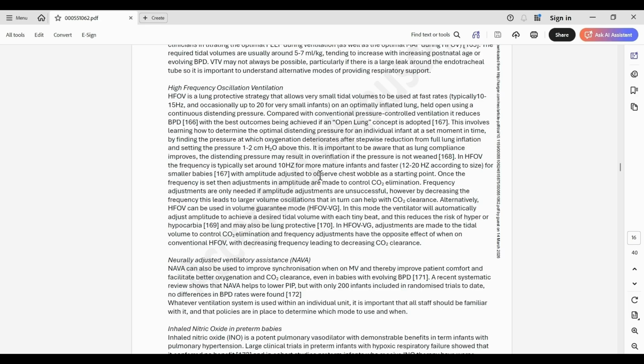But you can't just go ahead and throw kids on the ventilator or the oscillator without really knowing what we're doing with this. And this is, again, why we say at the very beginning, experience matters. You want to be at centers that are able to adjust these things. But then we look a little bit more closely at this. So we need to make sure we're weaning appropriately. The same 10 hertz for mature babies, a little bit more for that. And then we talk here about amplitude based on chest wiggle factor, which I'm going to hold a thought on. Frequencies are based on CO2 elimination. So amplitude is made to control elimination. That's appropriate. Frequencies are only changed if your amplitude is not adequate, which is an important one too.